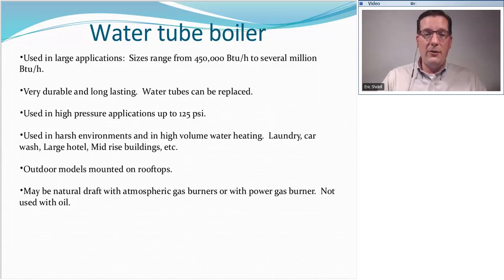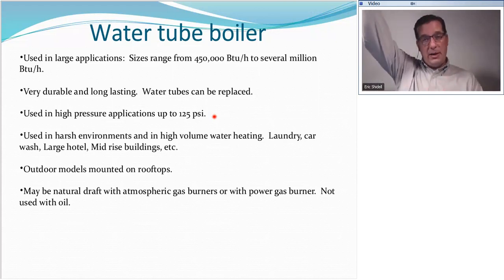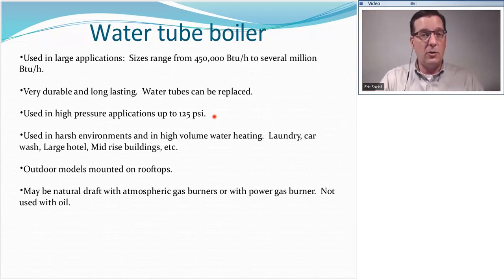But one of their advantages is that they can be used in high pressure applications. This means tall buildings where the boiler's in the basement, for example. This also means any other unusual application where we need higher than normal water pressure in the boiler system. Up to 125 PSI, these boilers can withstand. The cast iron boilers that we looked at before, they generally have a maximum working pressure of 30 PSI, sometimes 50 PSI. Same thing on the copper fin tubes. Generally, those have a maximum pressure of 30 PSI. But here on the water tube boilers, we can tolerate much higher pressures if the application demands it.